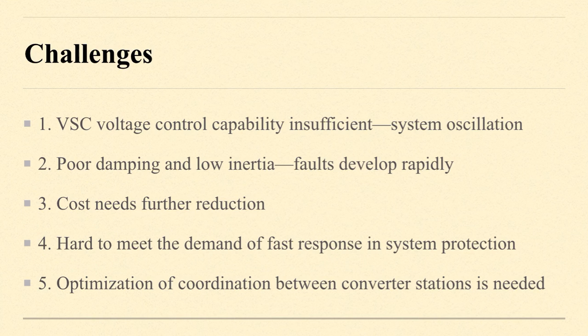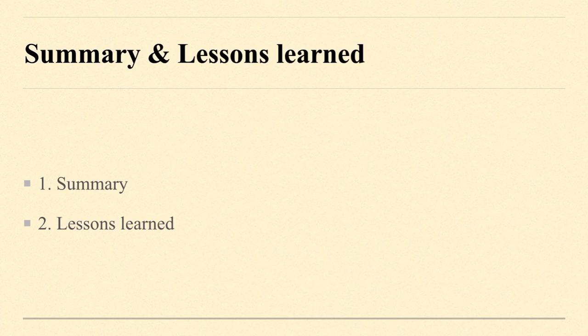And the converters are beyond current control, and the active power is determined by external systems. So when an island is operating at full power, surplus power from the failure of external system can extend failure regions. And here's the last part, the summary and lessons learned.